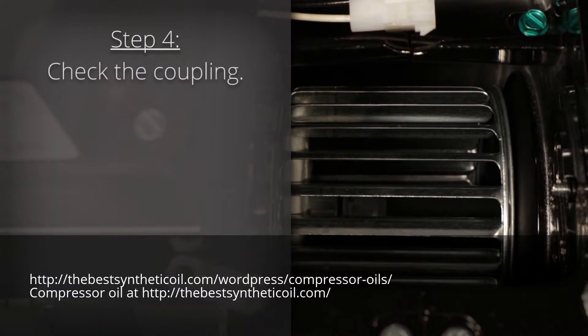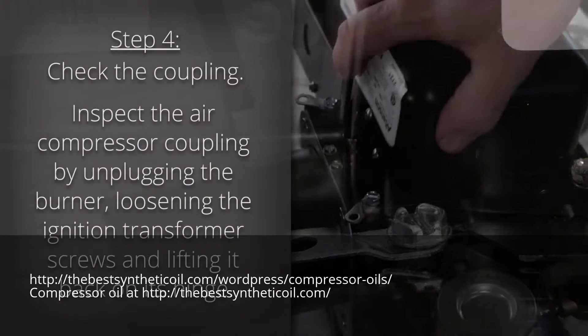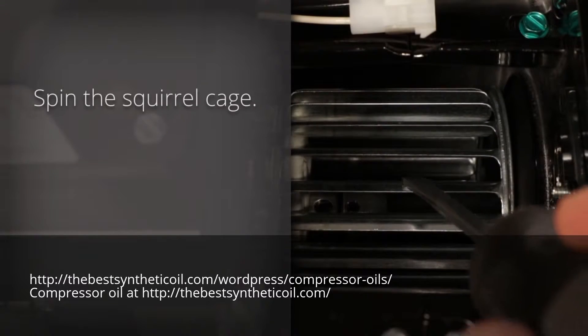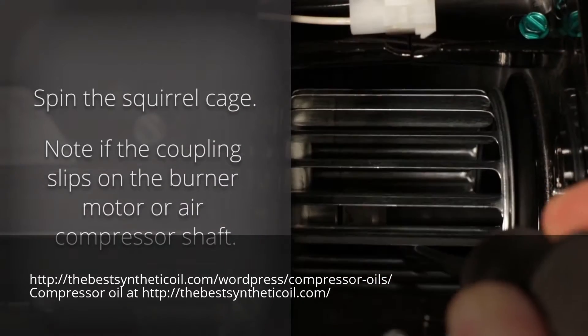Step 4: Check the coupling. Inspect the air compressor coupling by unplugging the burner, loosening the ignition transformer screws, and lifting it back on its hinge. Then spin the squirrel cage and note if the coupling slips on the burner motor or air compressor shaft. If the coupling is slipping, use your 1/8 inch Allen wrench to tighten the set screw.